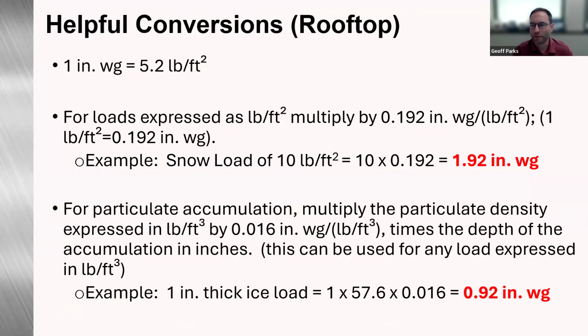Couple useful conversions when you're working with ductwork up on the roof. 1-inch water gauge equals 5.2 pounds per square foot. I don't know if you recall, probably not, in the first or second seminar when we talked about sizing tie rods. So this 5.2 pounds per square foot is something you would use in that equation.